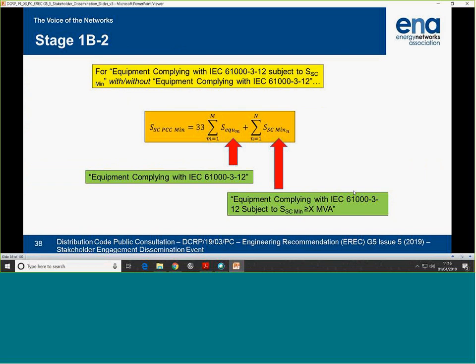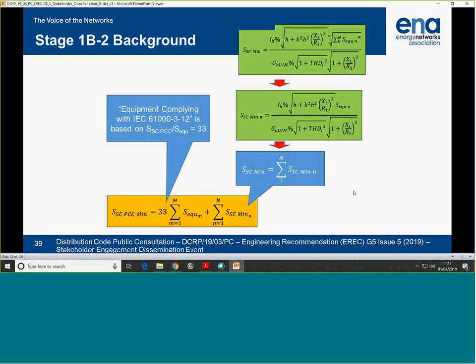The next 1B is for the case of equipment where they actually state the fault level is required. In this case, what we're doing is splitting it into two things. You've got the treatment of where they've required a fault level. That's on the right side of the equation. And you've got the one where they're saying it just complies with 312 on the left. So rather than using the more complicated formula we had with the F factor in 1B1, we've actually just used 33 times. The fault level aspect is much bigger in the right-hand term, so it tends to dominate anyway, so it doesn't matter. What you're doing is adding the fault levels required together, ultimately, if you've got multiple items. That's what you're doing. The basis is here, it's all written up in the background document, and it's basically, you get the required fault level from this relation. So that's stage 1 covered.